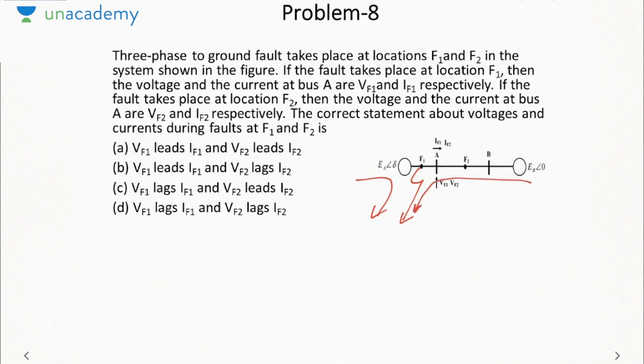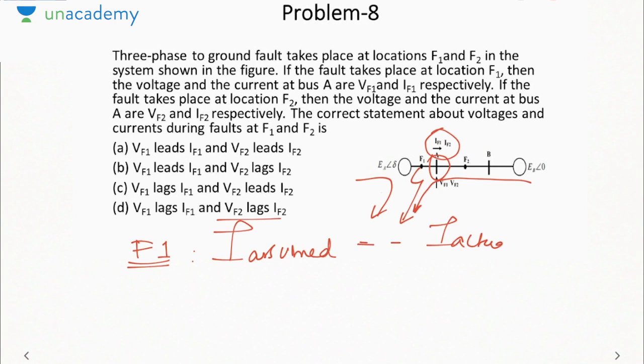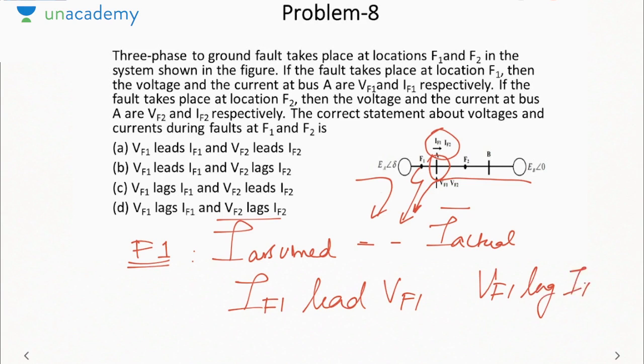Okay, so first I am assuming the fault at F1. Now take the bus A. Here IF1 and IF2 have been shown from left to right. But if you see, when the fault occurs at F1, the current at bus A is from right to left. That is, I assumed is equal to minus I actual. Both are in opposite directions. So here IF1 will lead VF1. Whenever the direction is opposite to the actual direction, the current will lead the voltage, or we can say VF1 will lag IF1.